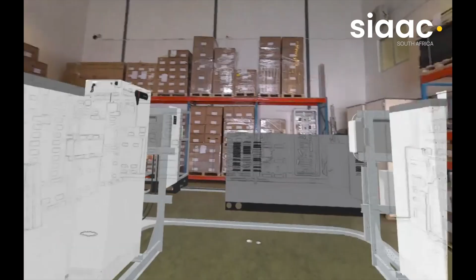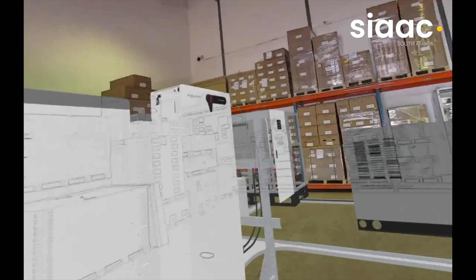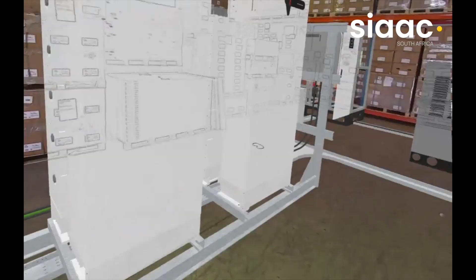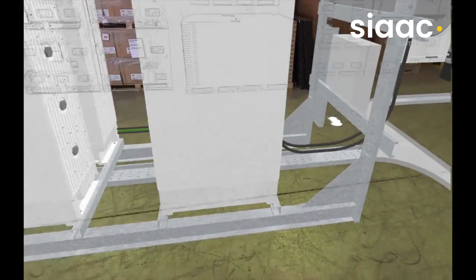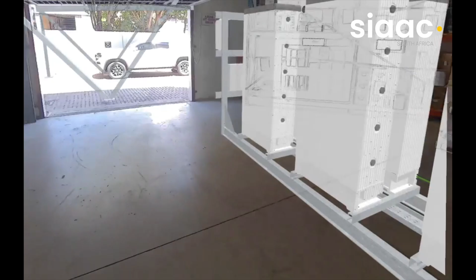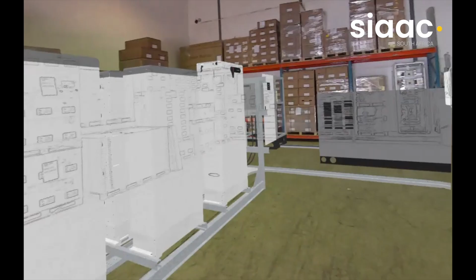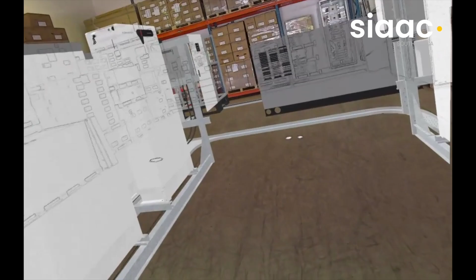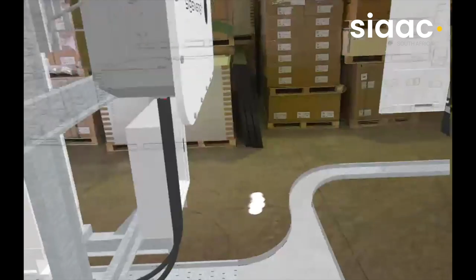Again, if we take all of our engineering effort over the 2 days that we needed, each element in this, from the tiniest battery base to the inverter, to the controller, each one of these elements were programmed to know what they are, what they're for, and they would all adhere to SANS regulation, wiring regulations, building code regulations, and also the manufacturer installation specifications. For example, if I try and place a battery base inside of its allowed clearance or outside of its allowed clearance to its neighbor or to a wall, it would highlight red and simply tell me I'm too close. If I try and run my cable system next to a water pipe, it'll tell me, according to this and that paragraph in the regulation, you are absolutely not allowed to do that.